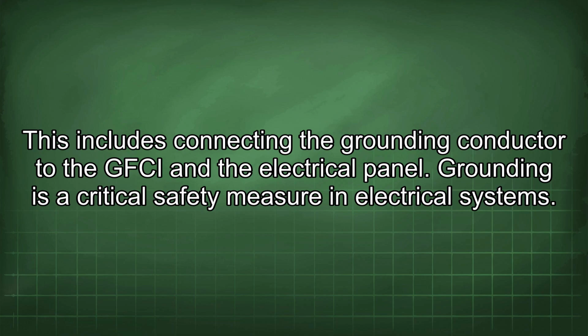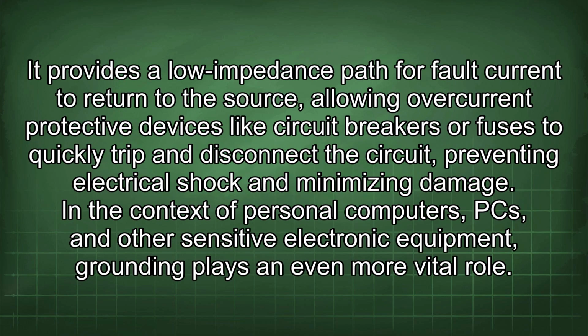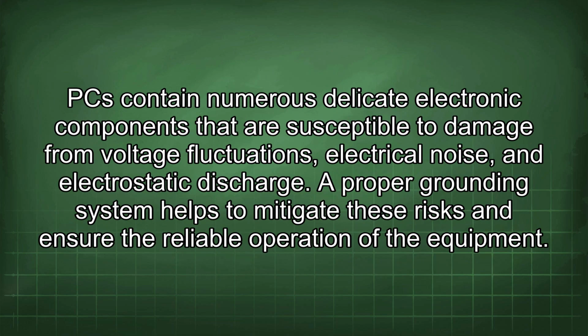Grounding is a critical safety measure in electrical systems. It provides a low impedance path for fault current to return to the source, allowing overcurrent protective devices like circuit breakers or fuses to quickly trip and disconnect the circuit, preventing electrical shock and minimizing damage. In the context of personal computers, PCs, and other sensitive electronic equipment, grounding plays an even more vital role. PCs contain numerous delicate electronic components that are susceptible to damage from voltage fluctuations, electrical noise, and electrostatic discharge. A proper grounding system helps to mitigate these risks and ensure the reliable operation of the equipment.